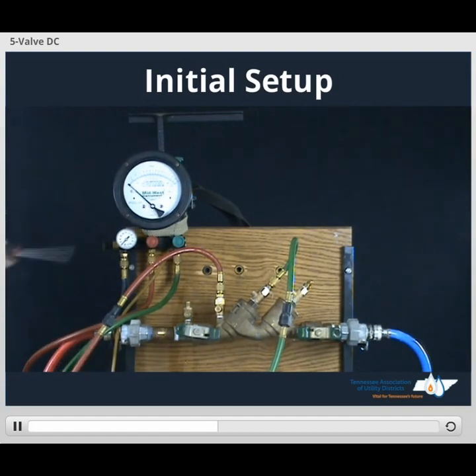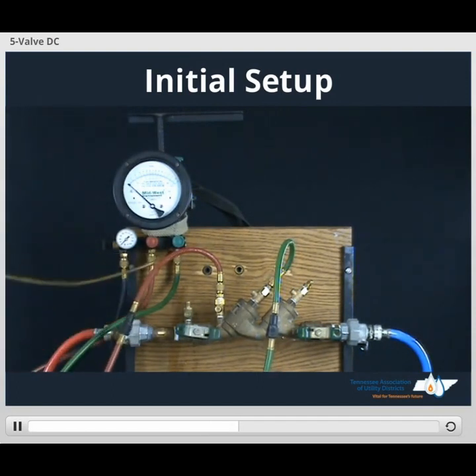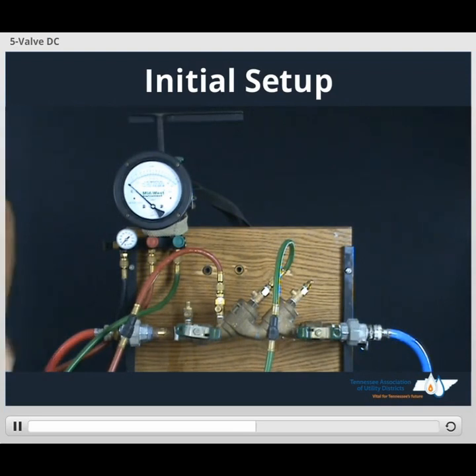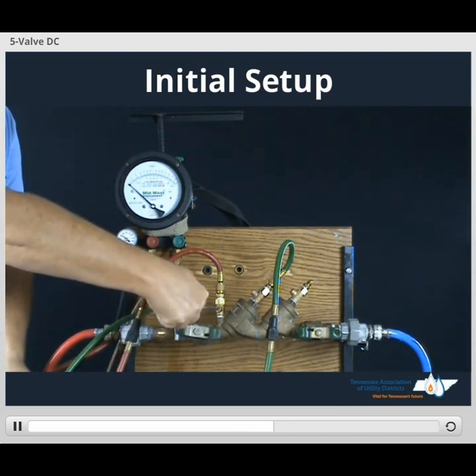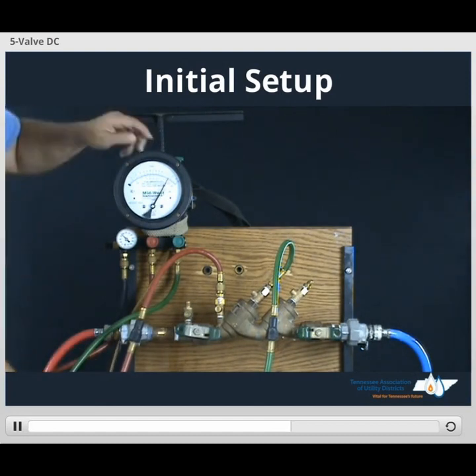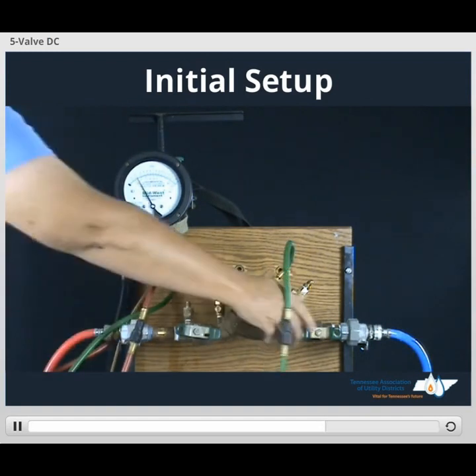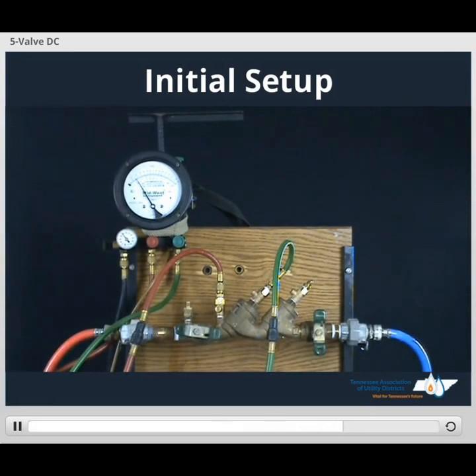Take our screwdriver, open test cock number 3. Take our bypass hose and secure it. We'll open up our low side lead. Take our screwdriver and open up test cock number 2. We'll open up our high side lead, close high side lead, and close low side lead. We're ready to turn off number 2 shutoff valve — that completes our initial setup, ready to begin our first test.